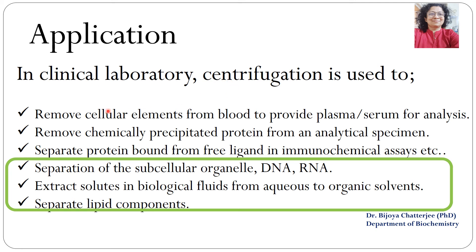Applications of ultracentrifugation in the clinical laboratory include: removing cellular elements from blood (achievable with a normal centrifuge to provide plasma or serum); chemically precipitating protein from analytical specimens (also achievable by normal speed centrifuge); separating protein-bound free ligand in immunochemical assays; separation of subcellular organelles; extraction of solutes from biological fluid; transfer from aqueous to organic solvents; and separating lipid components — the last several requiring high speed centrifuges and ultracentrifuges.